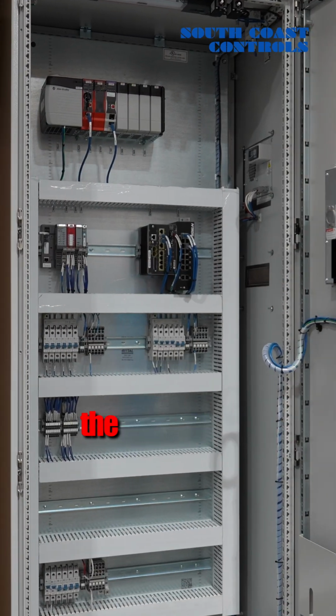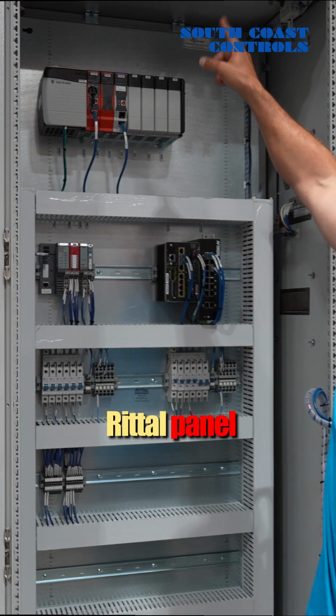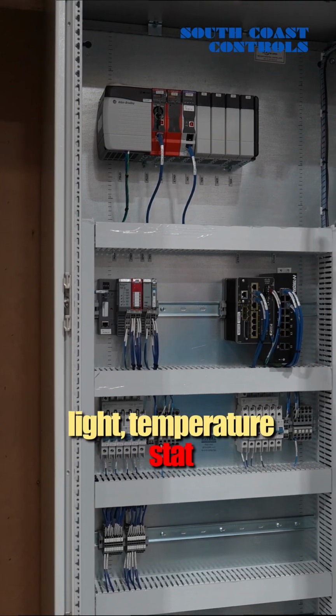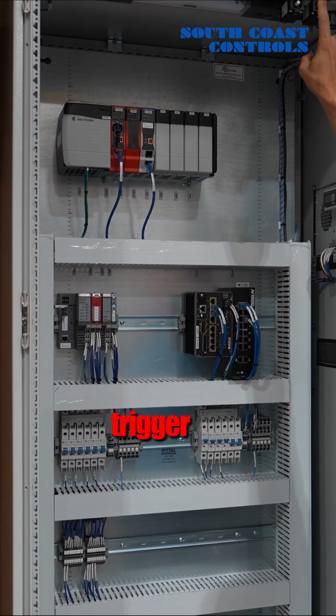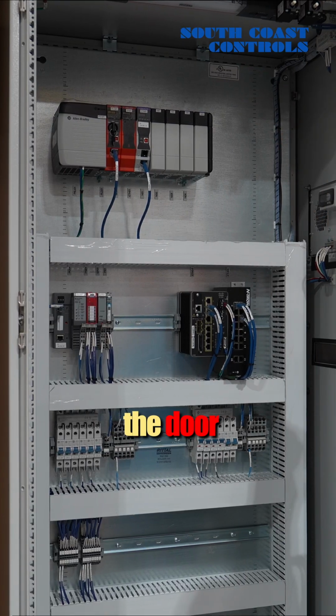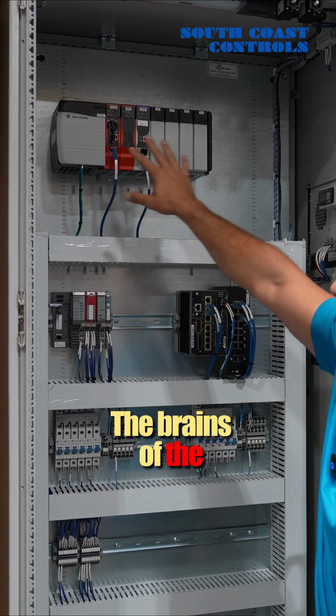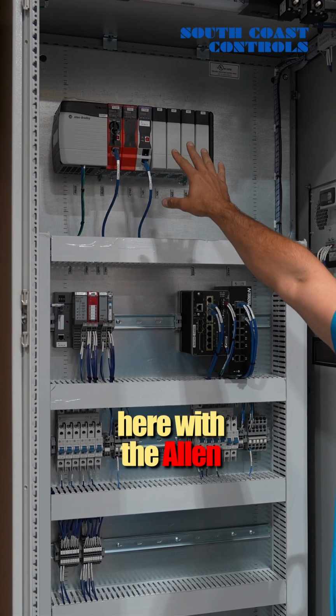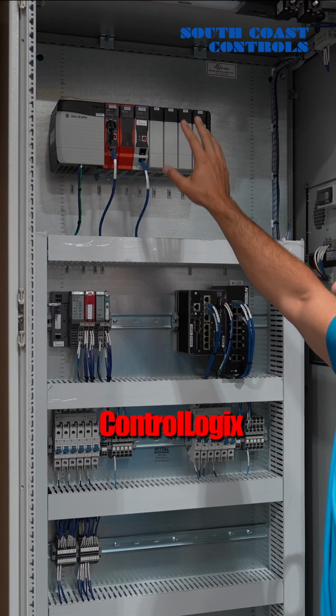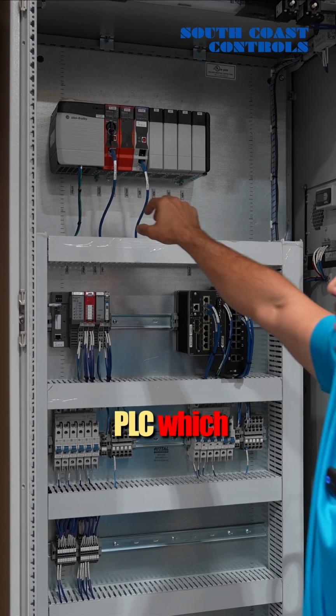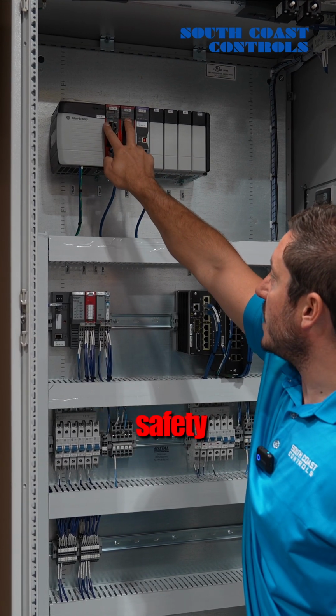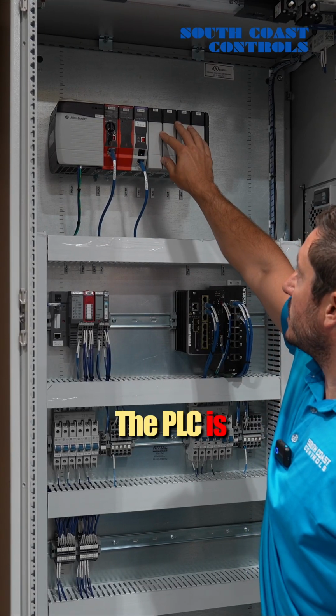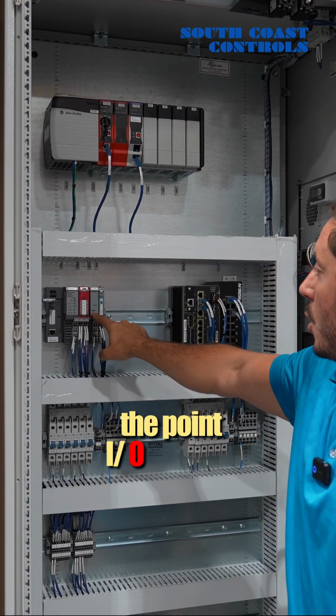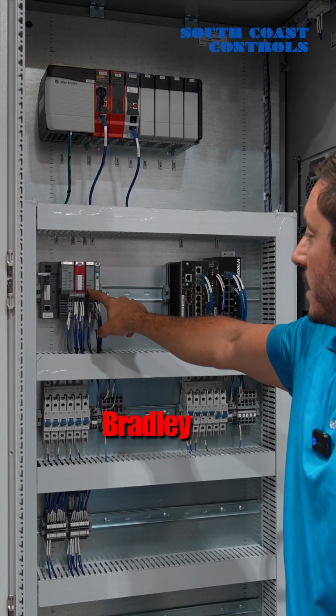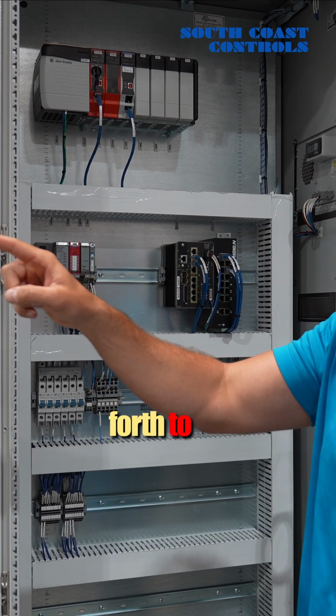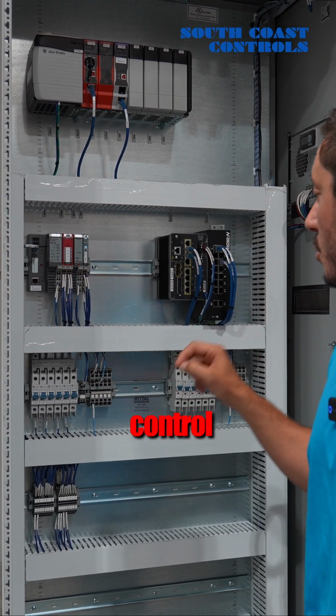Inside the cabinet on the top, it comes with a Rittal panel mounted light, temperature stat, and then the limit switches that will trigger the light to turn on when the door is open. The brains of the entire application are here with the Allen Bradley 1756 ControlLogix PLC, which comes incorporated with 2 safety cards. The PLC is connected via Ethernet down to the Point IO module here from Rockwell Allen Bradley that'll be communicating back and forth to the 6-bay system and the main control panel.